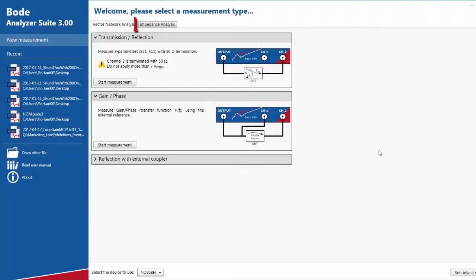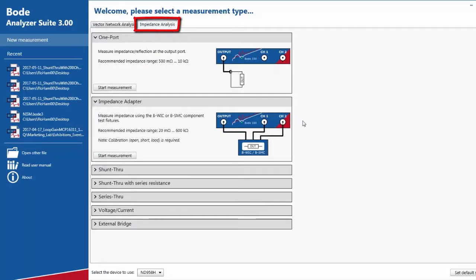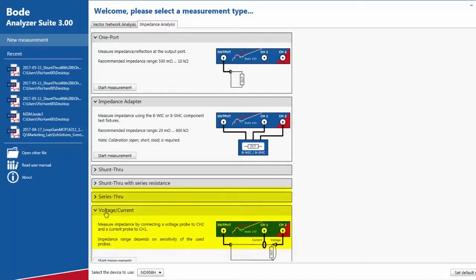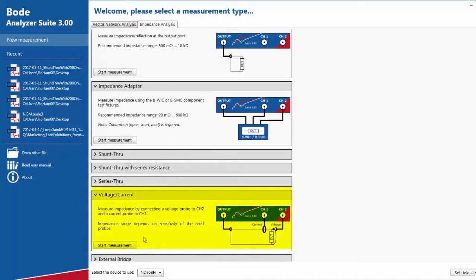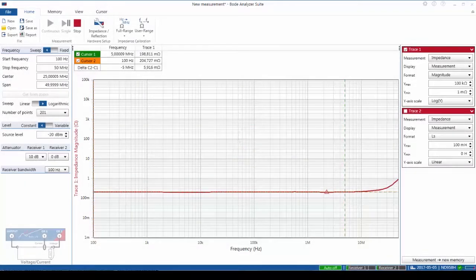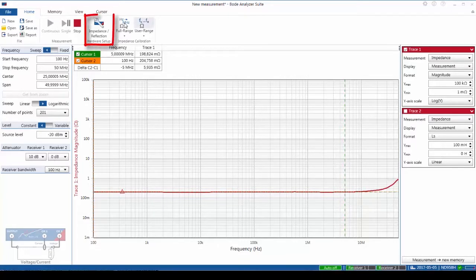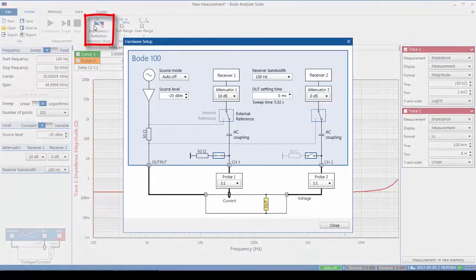First, from the welcome screen, choose the impedance analysis menu and then scroll down to find the voltage over current measurement and start the measurement. With everything connected, let's go ahead and look at the hardware setup.